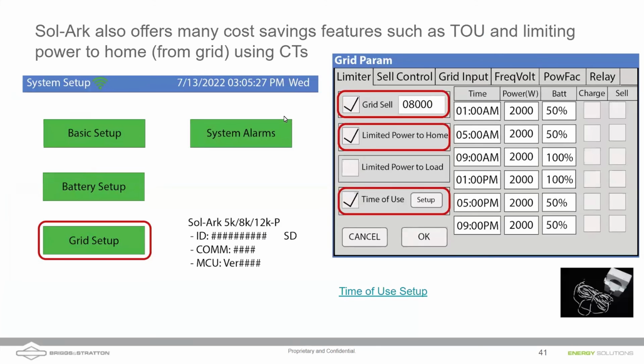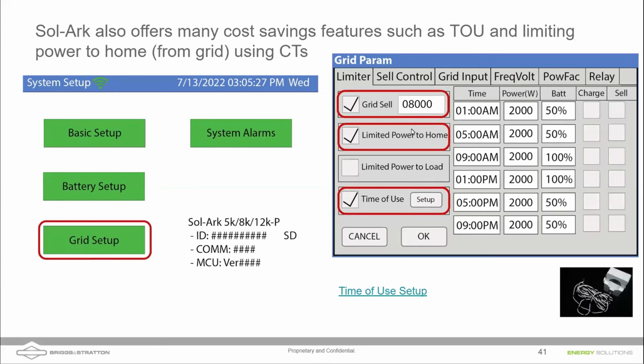So I would say on a couple of things, on one, when you have the restart at 31%, I would come into these time of use settings and overnight have a grid charge set at 32%, so that the battery goes all the way down to 32% and does a maintenance charge overnight, keeping the battery at 32%. If you programmed a 31% start percentage, it'll charge the batteries up mostly full if you hit it. So you can avoid that start percentage by programming time of use. It's a seasonal controller, so you get a summer and winter season with that.